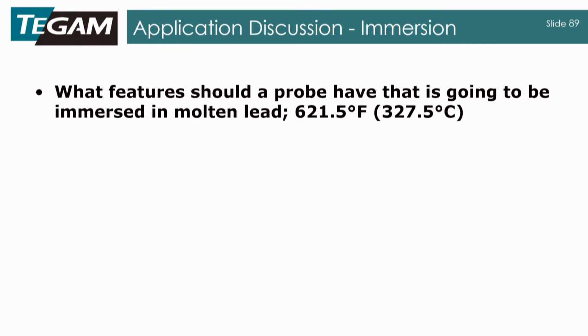So, pop quiz time. What features should a probe have that's going to be immersed in molten lead? And molten lead is at 621.5 degrees Fahrenheit or 327.5 degrees C. And I'll just go through and give you my recommendations here. For the handle, you're going to want a metal handle. The person using it is going to want gloves, or they also make metal handles with a ceramic transition. And as I said before, something that we didn't note here is how long is the probe going to be immersed in molten lead? And that would be something you'd want to consider in this application.